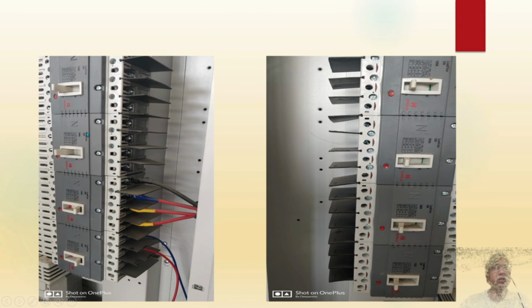Here's another place where the wires are going. Any wire from 6 mm up to 18, 20, or 25 mm can go here, but any wire going to 50-100 amps requires lugs or an adapter or spider link so it can fit between these flaps. These flaps are there so a short circuit doesn't happen in the MCB - the wires have to go inside here. So you need to know how much wire you have if you're going for this kind of product, so you don't get stuck with a local electrician, or make sure the electrician is competent enough to handle it.